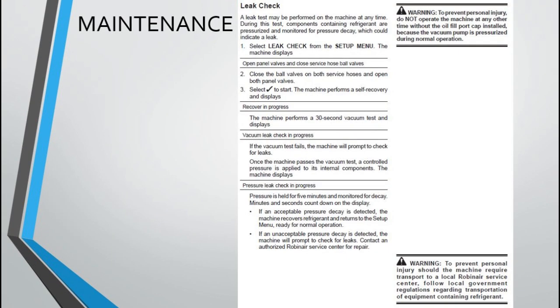Leak check. A leak test may be performed on the machine at any time. Select leak check from the setup menu. Close the ball valves on both service hoses and open both panel valves. Select check to start. The machine performs a self-recovery and displays. The machine performs a 30-second vacuum test and displays. If the vacuum test fails, the machine will prompt to check for leaks. Pressure is held for 5 minutes and monitored for decay.